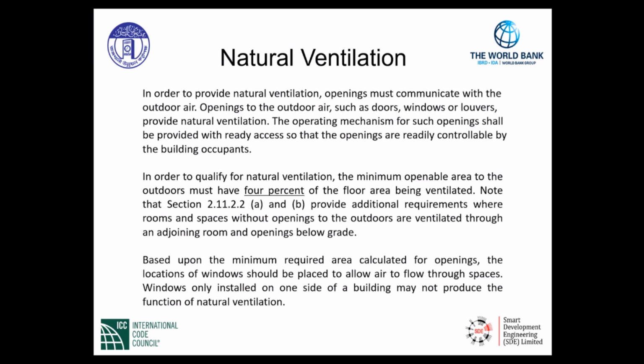Based upon the minimum required area calculated for openings, the locations of windows should be placed to allow air to flow through spaces. Windows only installed on one side of the building may not produce the function of natural ventilation. In other words, we need cross ventilation to take in air possibly from one side of the building where we have pressure differentials, and provide some means to allow air to flow completely through the building from one side and out of the other side due to the pressure differentials.